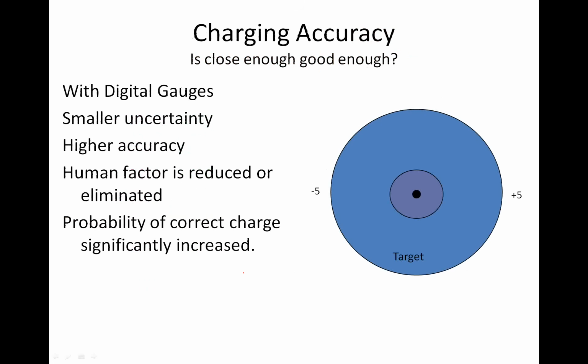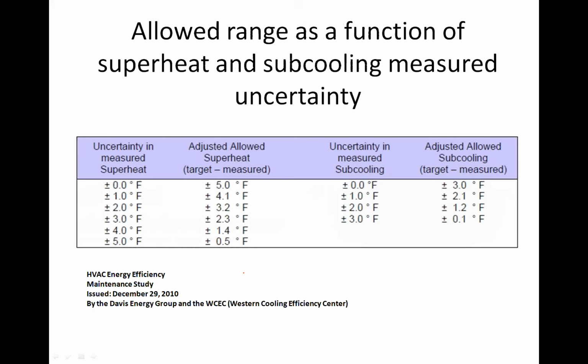With digital gauges, what we've essentially done is get a smaller uncertainty and a higher accuracy. And you have to remember, we've eliminated some human factor because we're not interpolating anymore off a temperature-pressure chart, and we're not trying to split hairs on a needle with a gauge. The gauge calculates right down to a tenth of a degree Fahrenheit, down to a tenth of a degree of superheat or subcooling, and a tenth of a psi. So the probability of correct charge is significantly increased.